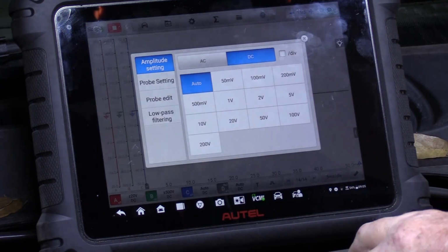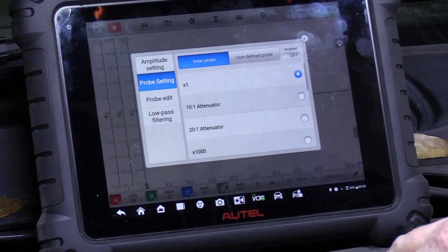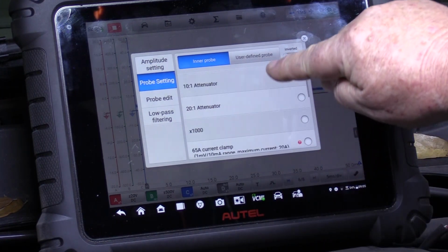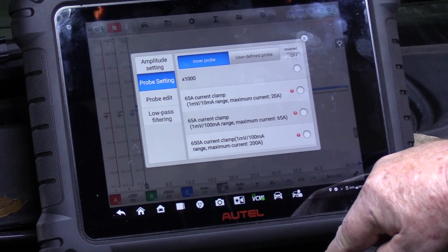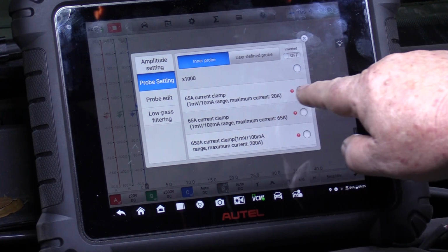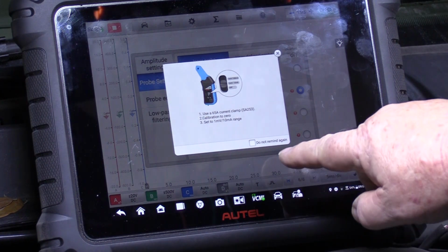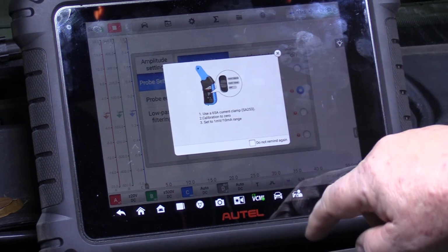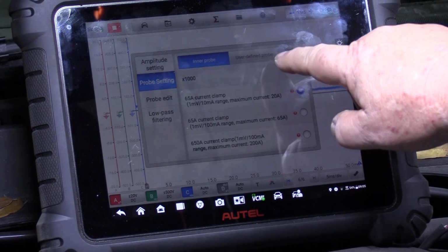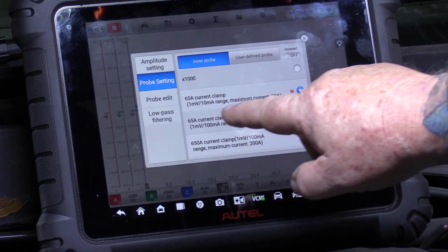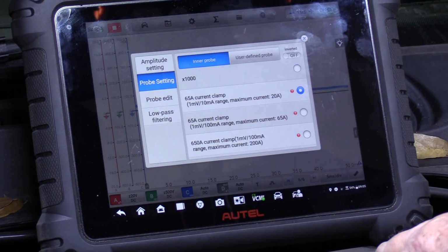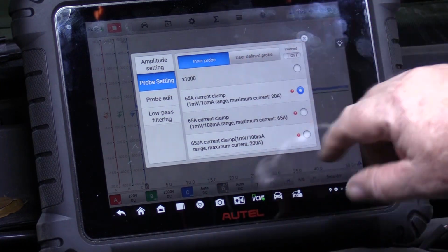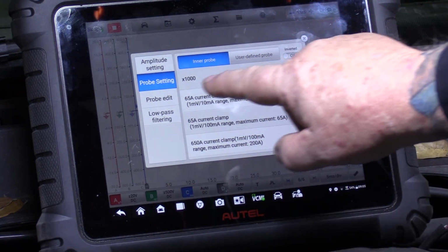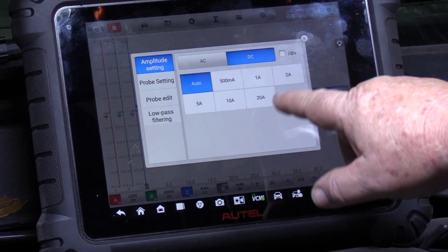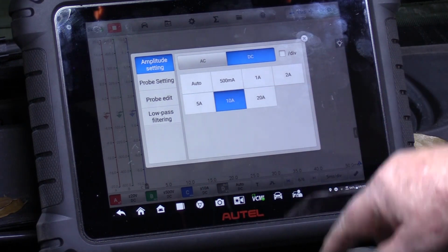For C, I'm going to do something a little different here. I'm going to select a current clamp, a low current clamp to be precise, and we're going to go to the 1 millivolt range, which equals 10 milliamps. We're going to set the probe here. Now it's going to do the scaling for me, so I don't have to worry about that. Then we'll go to amplitude setting. Again, we'll start with 10 amps and see where that takes us.